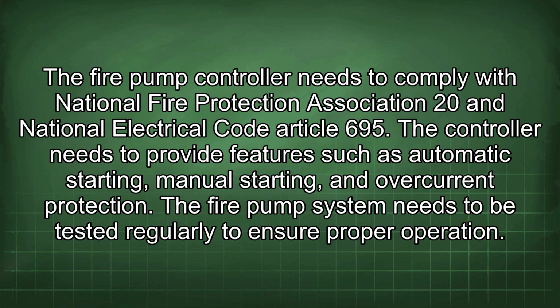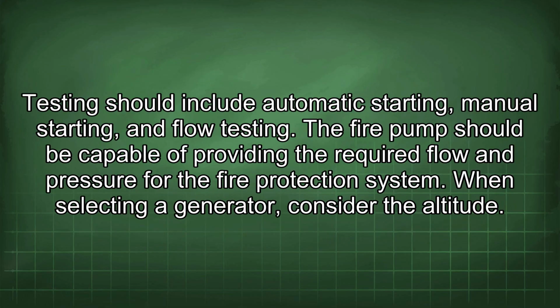The fire pump controller needs to comply with National Fire Protection Association 20 and National Electrical Code Article 695. The controller needs to provide features such as automatic starting, manual starting, and overcurrent protection. The fire pump system needs to be tested regularly to ensure proper operation. Testing should include automatic starting, manual starting, and flow testing. The fire pump should be capable of providing the required flow and pressure for the fire protection system.